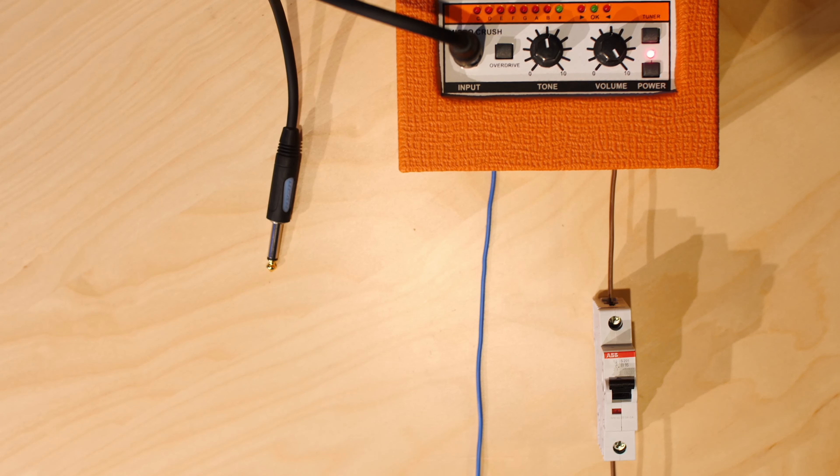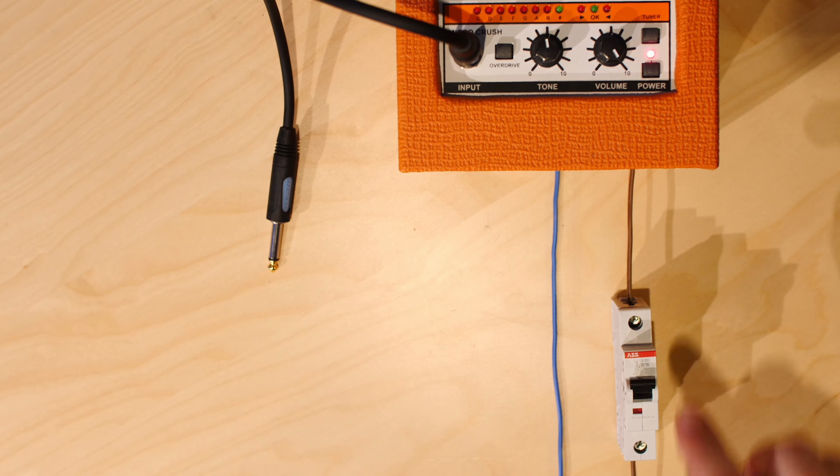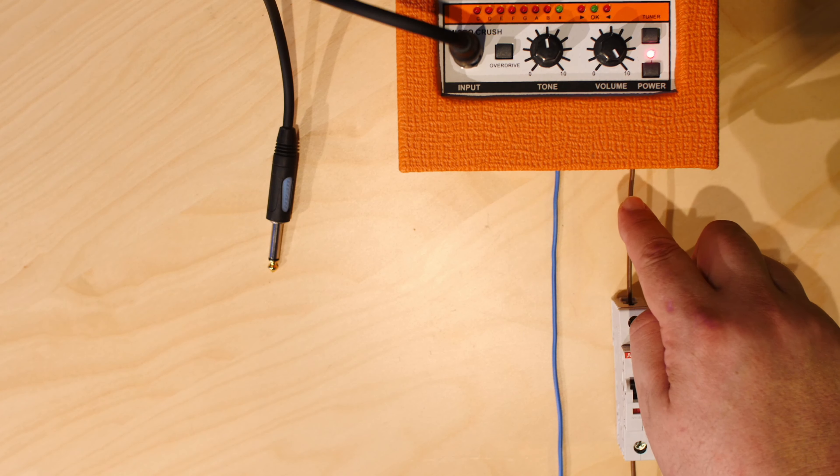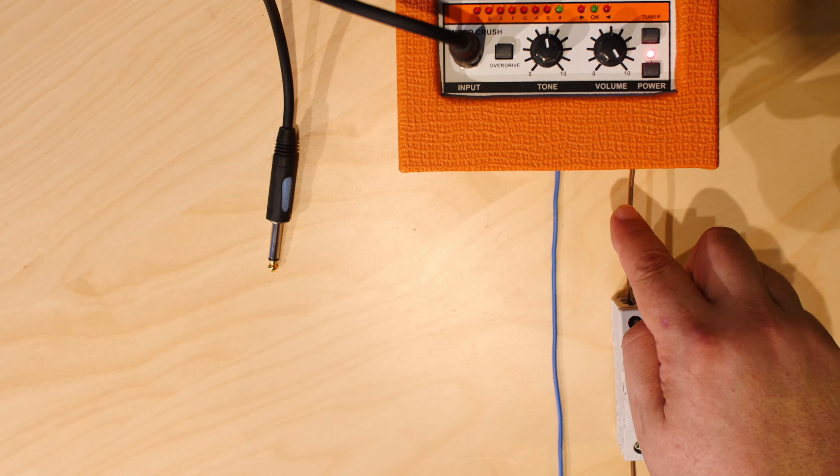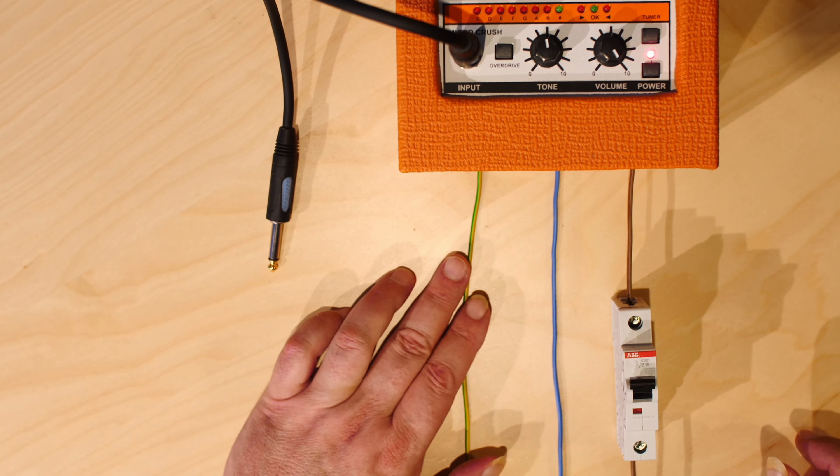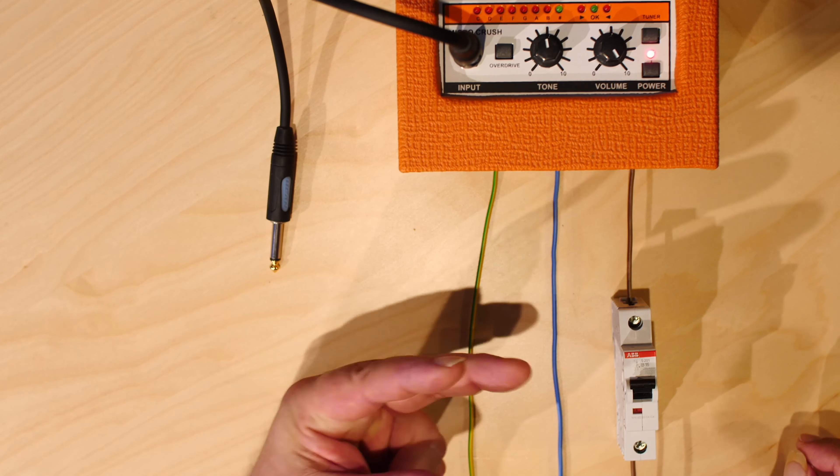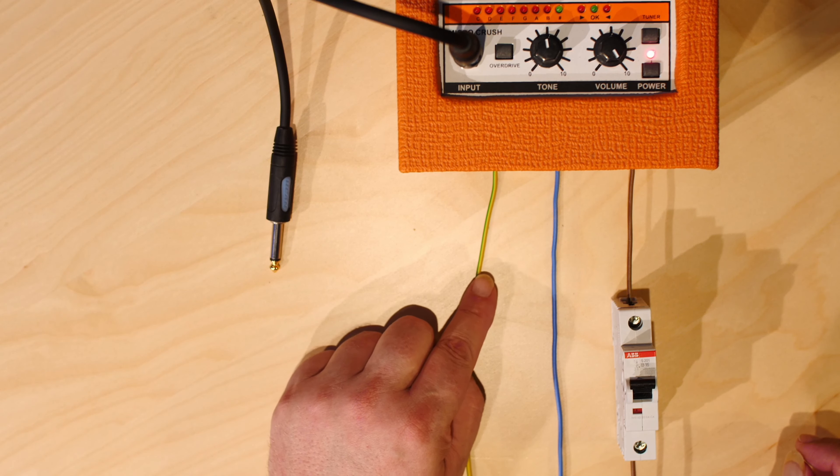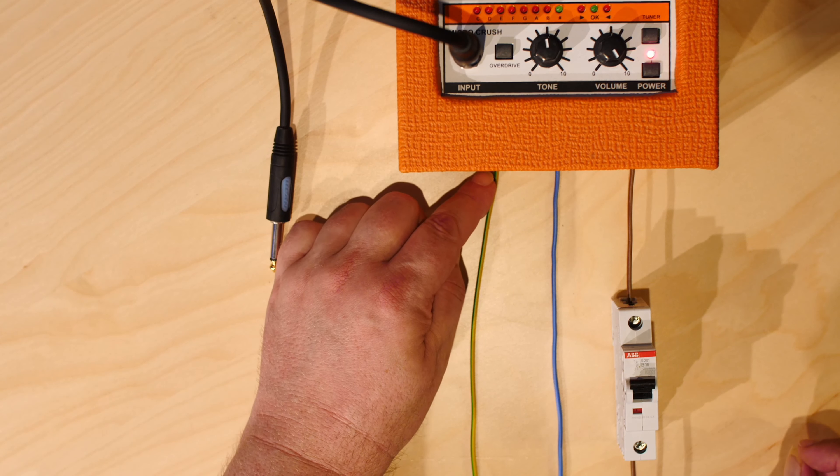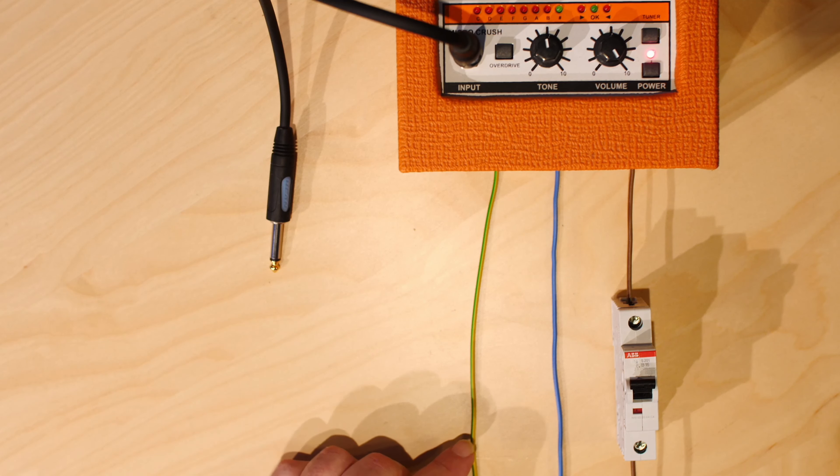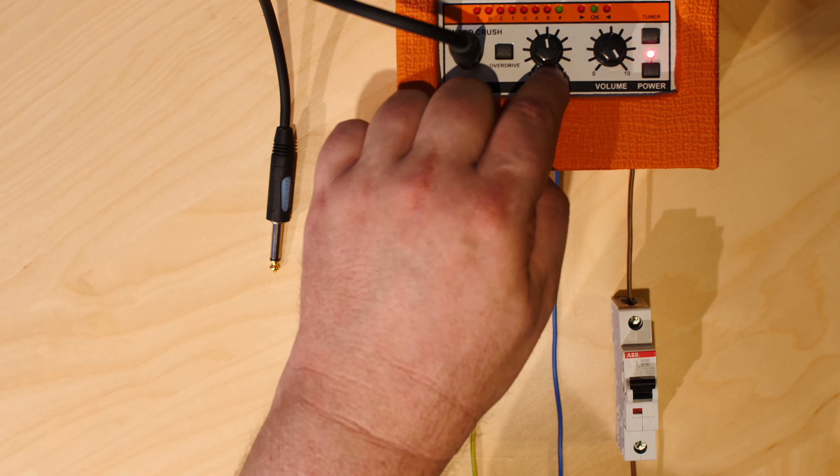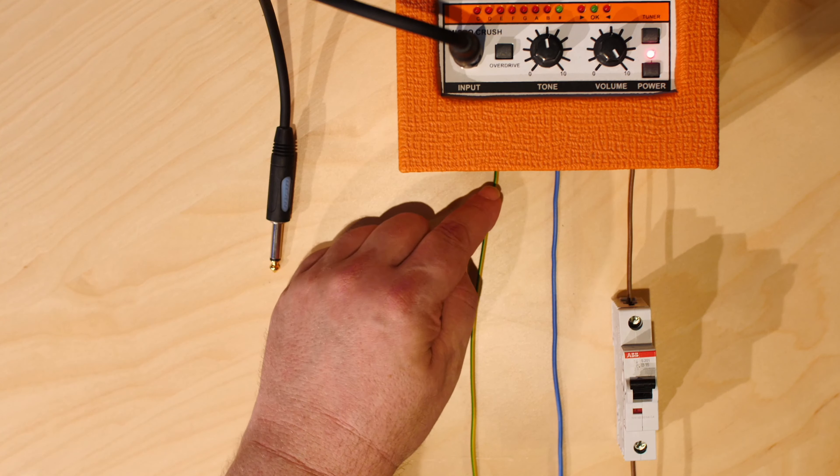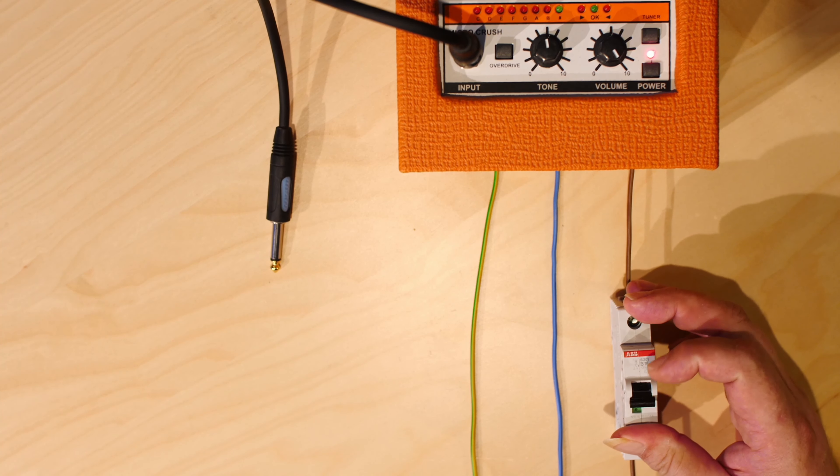Okay, so what do we do? First thing we should consider is, sadly, I know in Nepal, most installations, or often, I see that there's only two wires in your wall plug, and that poses a big danger, because if we had three wires, this one is called protective earth. And if we have a three-pin prong in the wall socket, one of them should be the protected earth, and this is connected to the metal chassis. And if there's basically a 0 ohm resistance, there's no resistance at all, so if there comes the electricity, for some problem, it goes into the metal chassis, and from the metal chassis here, there's basically no resistance, there will be a huge current flowing, that is enough to switch the breaker off.